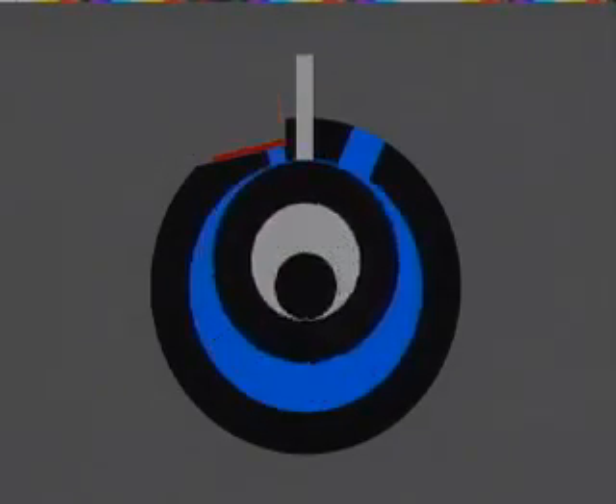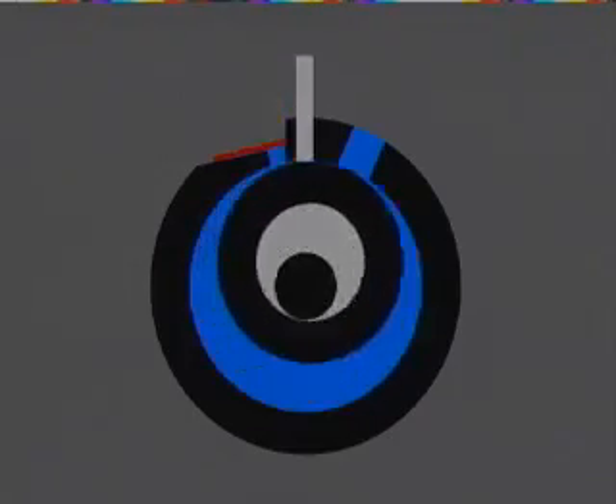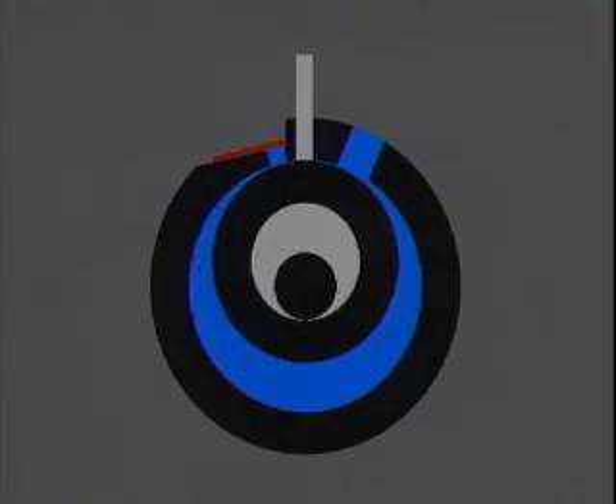Compression and suction occur simultaneously on opposite sides of the rolling piston, so it takes 2 full revolutions of the shaft to draw in and compress a volume of vapor. Let's start with the rolling piston at top dead center.